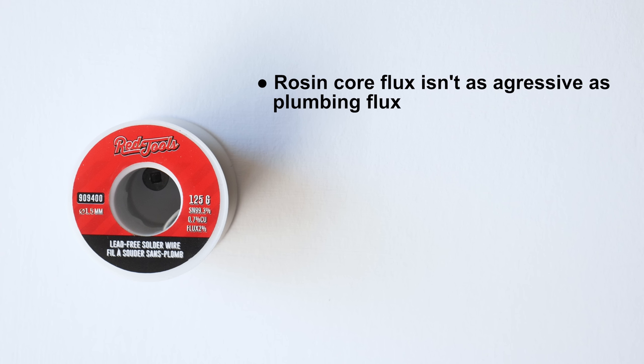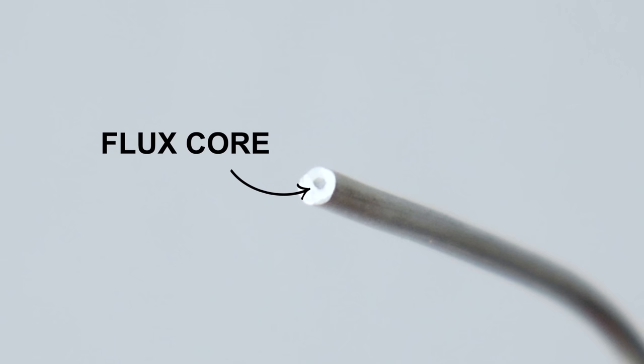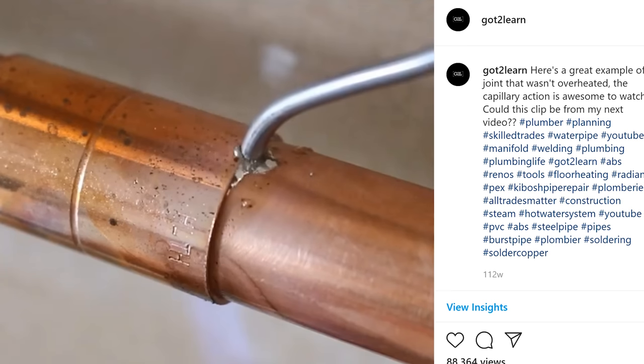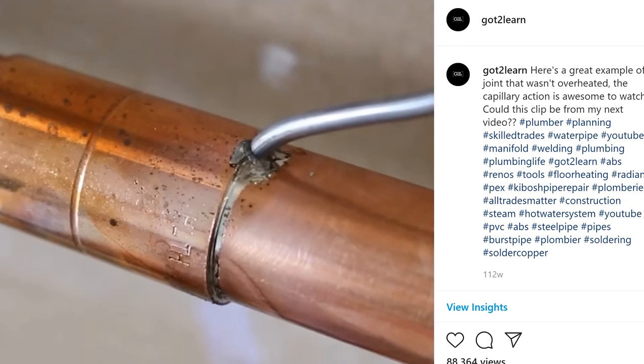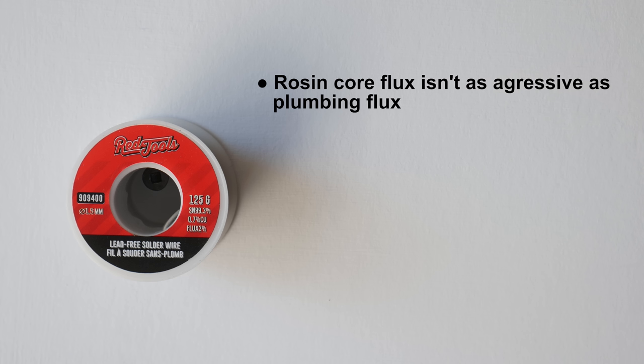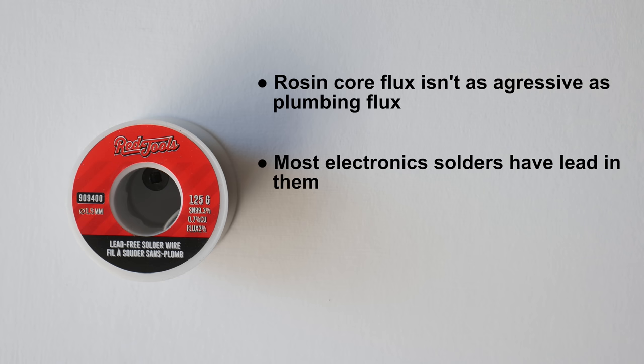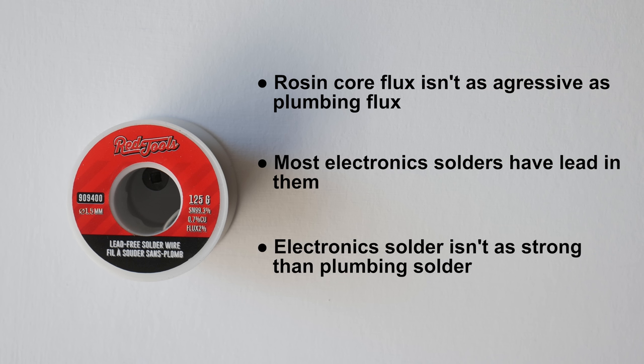The reasons you don't want to use electronic solder on plumbing are: rosin core flux is not nearly as aggressive as plumbing flux, so capillary action wouldn't be as good and might cause a leak. The other reason is that most electronic solder have lead in them, which is prohibited on potable lines. And lastly, the fact that it's weaker than plumbing solder. The joint wouldn't be as strong, which could cause leaks in the future, so just use the proper solder to be safe.